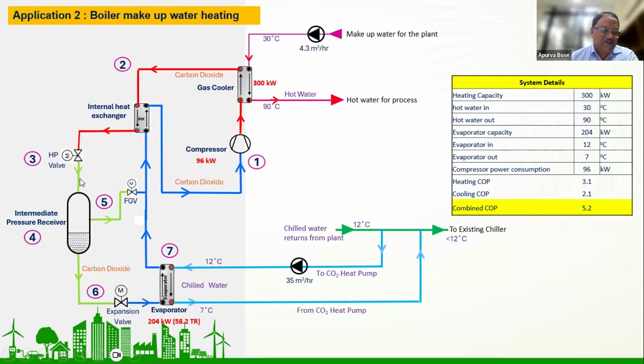Once it passes through that, obviously it gets expanded. So the pressure gets reduced to 50 bar and the temperature to 12 degrees Celsius when it moves to the intermediate pressure receiver here. Here the phase change happens. Some part of it is in gaseous form, CO2, and some part is in liquid form. And as I was mentioning, the gaseous part at 12 degrees Celsius, we flash it through a valve to this line, which is going to the internal heat exchanger. And from here, it goes back to the compressor. It is all in gaseous form.